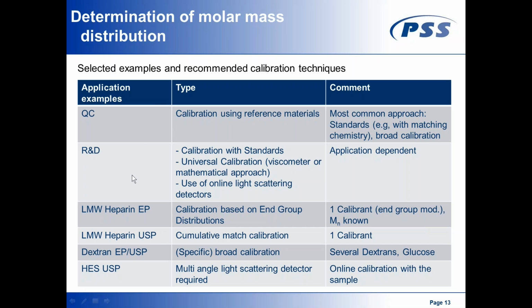When you look at R&D departments, you also see all kinds of approaches. You have calibration with standards, but you also have universal calibration, for example, where you use a viscosity detector or the mathematical approach. And also, of course, a lot of R&D labs use an online light scattering detector to measure the molar mass distribution. So getting the information you want is very, very application dependent. I just want to show one more application here, which is the application of hydroxyethyl starch for USP. Here, it's one of the rare examples where you have a quality control with a detector where you are required to use a multi-angle light scattering detector if you want to use the technique that is recommended by the USP.